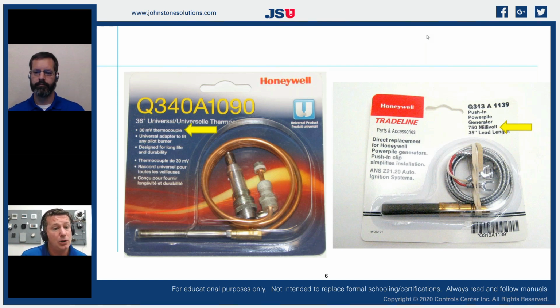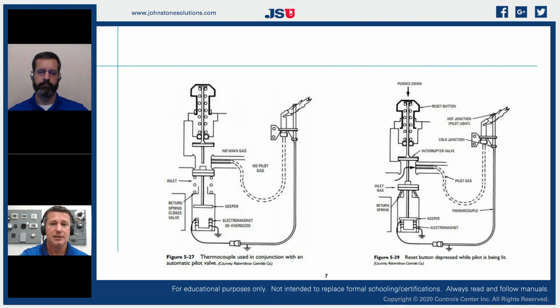If we're talking about larger commercial and industrial gas valves, they have much larger bodies, they move more volume, which means they need more pressure to hold the valve open. So it has a larger coil, larger solenoid, so it needs more voltage. So we use a power pile, which can generate 750 millivolts. So it generates that voltage to do work, okay? So if we look at a gas valve, as we're trying to light it, as we're trying to establish its control, on the gas valve button, we're going to apply pressure on that, which is going to push the plunger down.